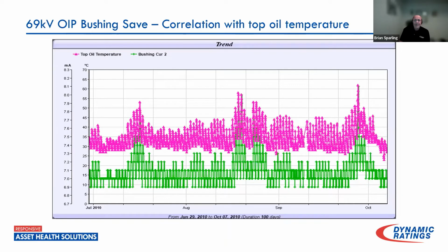The same data, but now correlated to top oil temperature of the transformer. And we're looking at here in pink is the top oil temperature. So in this case, every time the top oil temperature was going greater than 40 degrees C, the leakage current was increasing. And then as the transformer cooled down from a loading point of view or a day point of view, we see the leakage current decreasing.